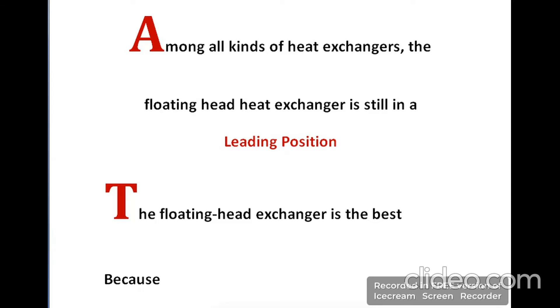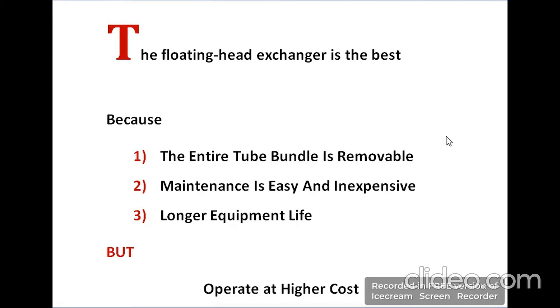Floating head heat exchangers are still at a leading position due to their versatile applications. Their leading position is due to some qualities. The first one is that the entire tube bundle is removable, which means we can clean it properly. So its maintenance is easy and inexpensive. It is a longer life equipment but its operating cost is higher.